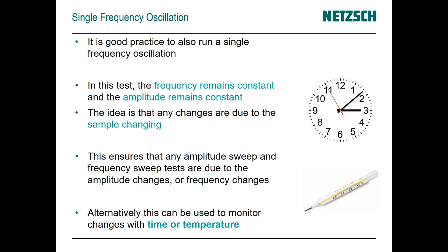Now let's talk about single frequency measurements. We talked about varying the frequency to look at effects of time on a material, but running things at a single frequency can also tell us quite a bit. If we hold the frequency constant and keep the amplitude constant, we can watch changes taking place in the material. For example, putting an adhesive or epoxy between the plates lets us monitor the curing process of that material with time — either isothermal or with changing temperature.